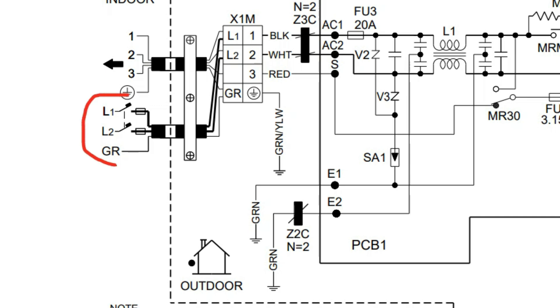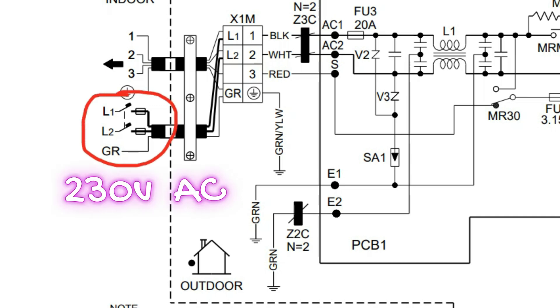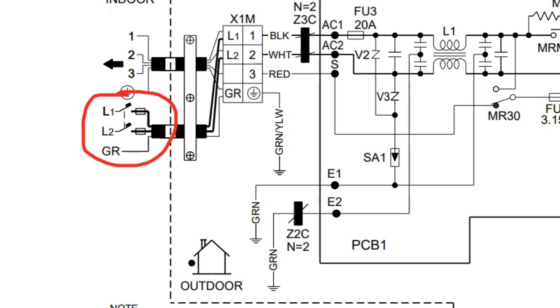Here we see leg 1 and leg 2, so that means we're dealing with 230 volts. On a side note, there are some mini-split systems — particularly smaller ones at 6,000, 9,000, or 12,000 BTUs — that might actually run on 120 volts. But anything higher than that is definitely going to be 230, and sometimes even the lower ones are also 230, so keep that in mind.